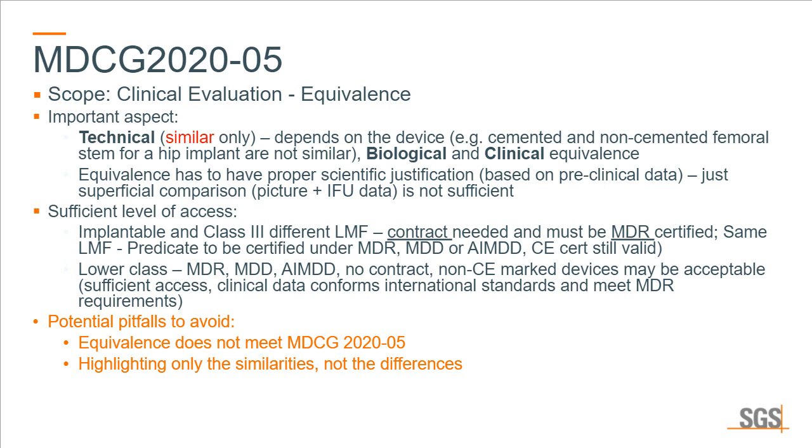So for implantable and class 3 devices from a different legal manufacturer, there's an explicit contract needed and the predicate device must be MDR certified. If it's from the same legal manufacturer, the predicate device can be certified under the MDD, MDR, AIMDD, and their CE certificates should still be valid. And of course, now that puts an extra spin because of the MDD validity extension situation.